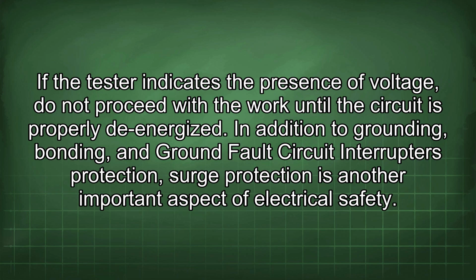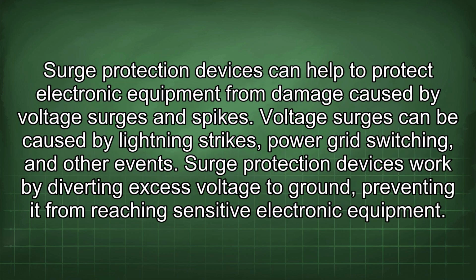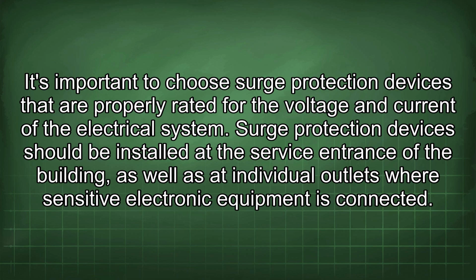In addition to grounding, bonding, and ground fault circuit interrupter protection, surge protection is another important aspect of electrical safety. Surge protection devices can help to protect electronic equipment from damage caused by voltage surges and spikes. Voltage surges can be caused by lightning strikes, power grid switching, and other events. Surge protection devices work by diverting excess voltage to ground, preventing it from reaching sensitive electronic equipment. It's important to choose surge protection devices that are properly rated for the voltage and current of the electrical system. Surge protection devices should be installed at the service entrance of the building, as well as at individual outlets where sensitive electronic equipment is connected.